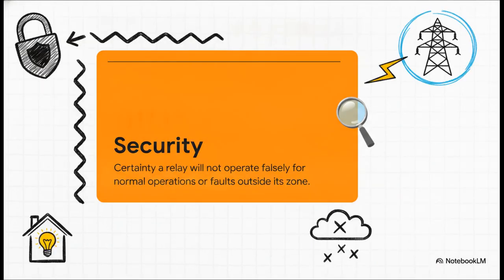And on the flip side, we have security. This is the absolute certainty that a protective relay will not operate falsely for normal operations or for faults that occur completely outside its designated zone. Prioritizing security means you're saying, I cannot afford a false alarm. Now, a security failure might not mean broken equipment, but it does mean angry customers sitting in the dark for absolutely no reason, creating unnecessary disruptions to the larger network.